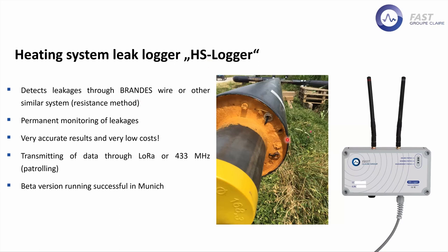So we use the wires from Brandes, connect them to our HS logger, and it's a permanent monitoring of the leakage. It runs multiple measurements during the day and also during the night. It measures the resistance between the two wires and also the single resistance of each wire.